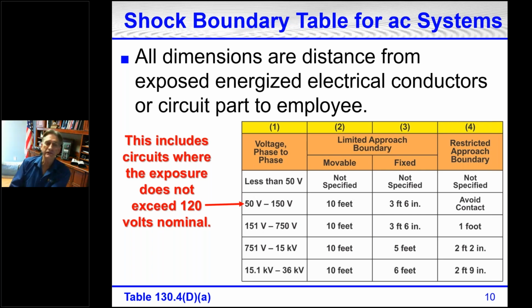Then we get to the second row, 50 volts to 150 volts. There's a footnote that goes along with that row, and it says this includes circuits where the exposure does not exceed 120 volts nominal.